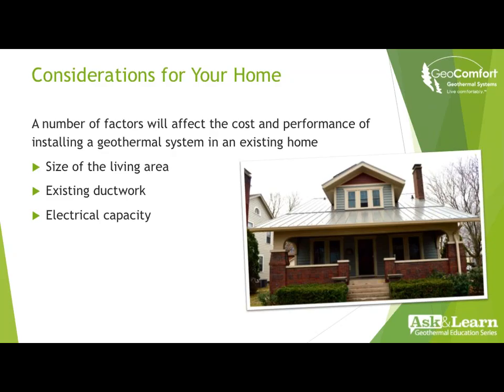Another thing to look at is electrical capacity. If we're taking a gas furnace out and putting in a full package geothermal unit, we'll use more electricity, but no gas. So we have to make sure we have enough ampacity to run the compressor and any electric resistance heat that augments the geothermal unit. And the insulation and weatherization are very key - the tighter the envelope, the smaller the unit, the less runtime, less operating costs, and less install costs.